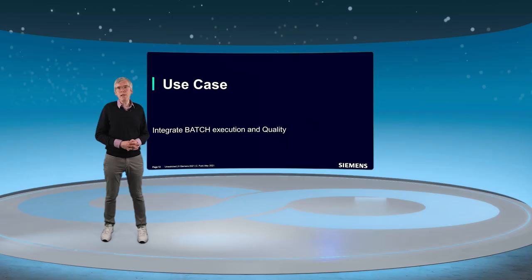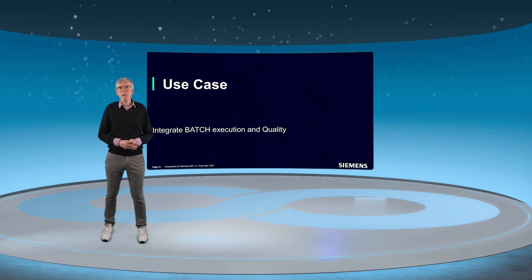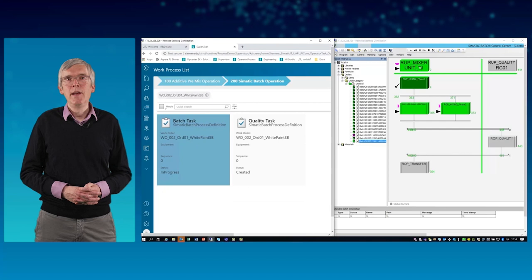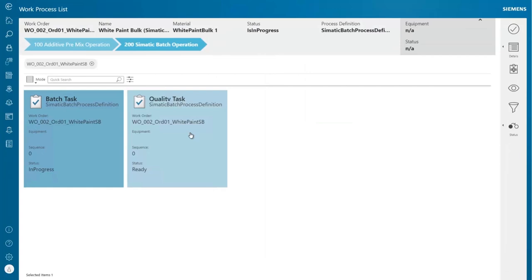The system automatically creates the SIMATIC Batch recipes based on the information and materials received from ERP. The operator activates the batch task and immediately SIMATIC PCS7 Batch starts execution on the automation level. The batch engine proceeds until it reaches a wait task, where it needs to wait for the results of an at-line quality test. In OPCenter, the quality task changes status from created to ready and the operator starts the quality task.